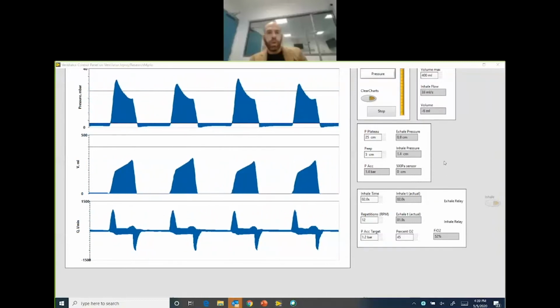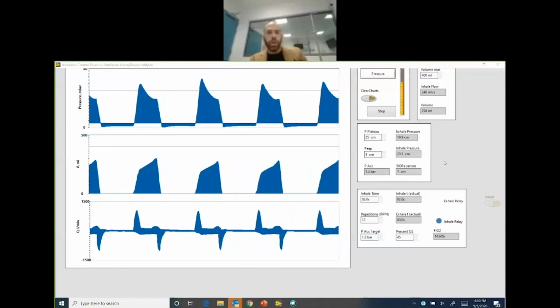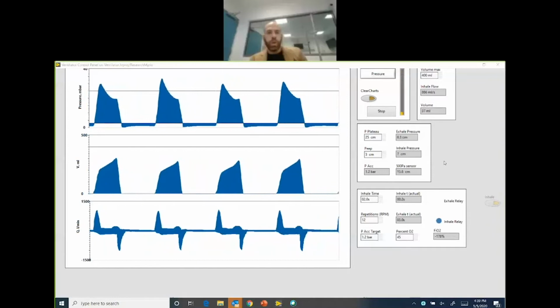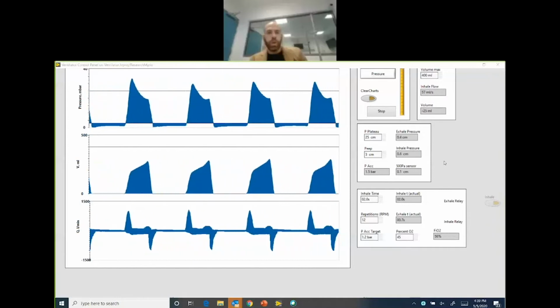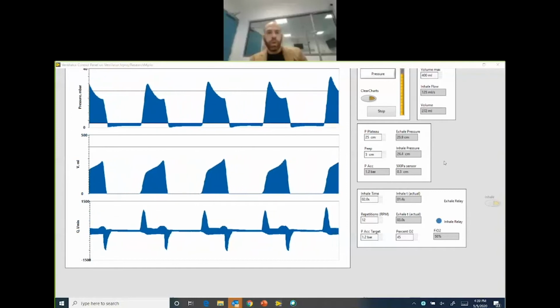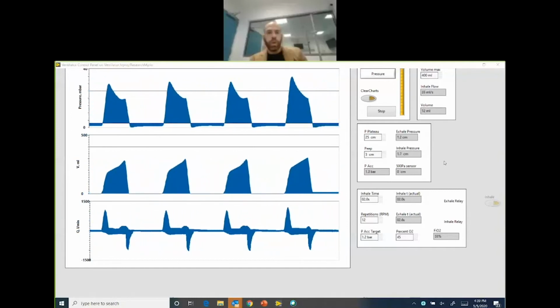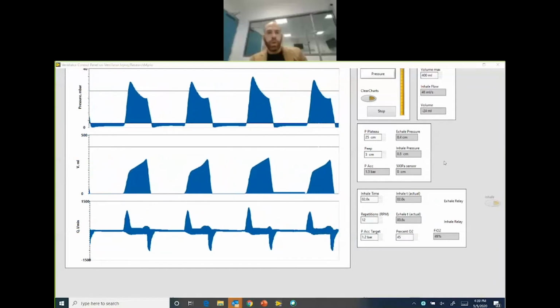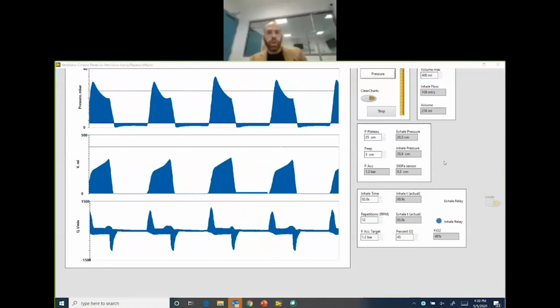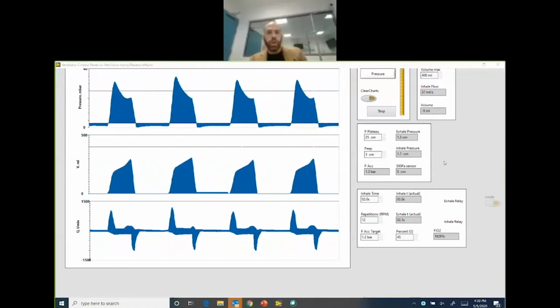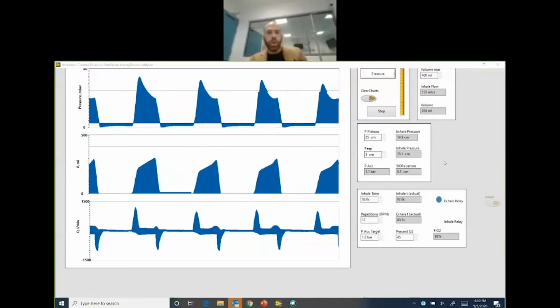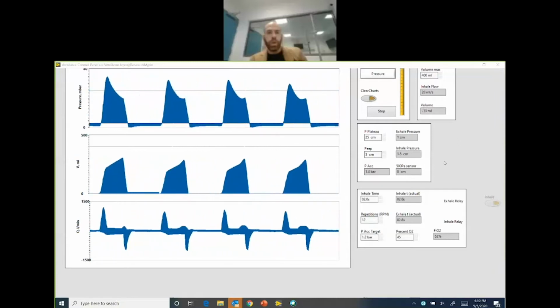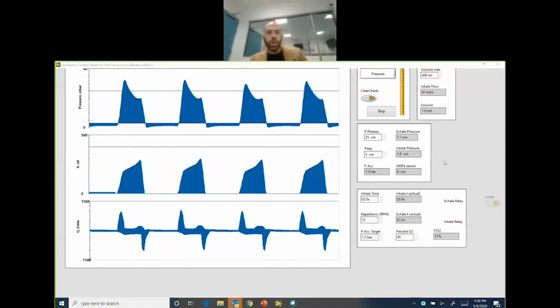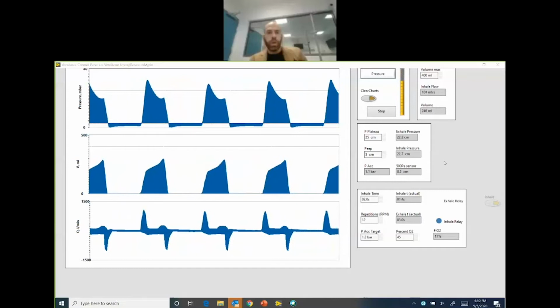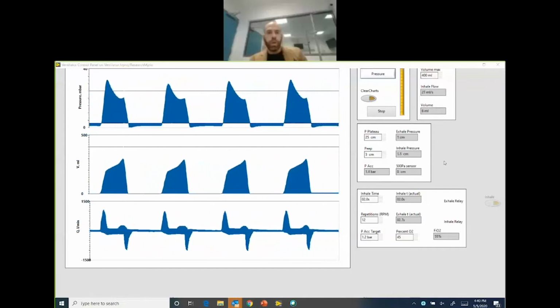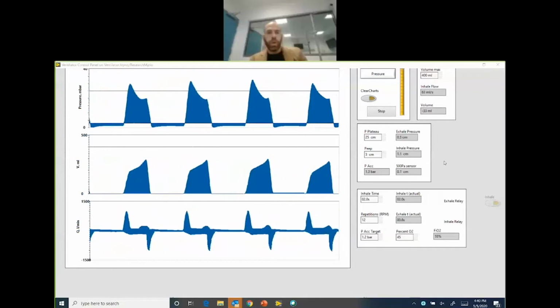But mostly the issue is that if the patient is not awake, then the ventilator typically is the driving force behind his breathing. So any mistake in the ventilator or any problem with the components of the ventilator could lead to injury. So from the get-go, we designed our system to follow the most strict safety rules possible. In that intent, we used the same approach that commercial ventilators use, an open valve for the exhale, which means that if there is a problem and the patient wants to breathe by himself, he can.